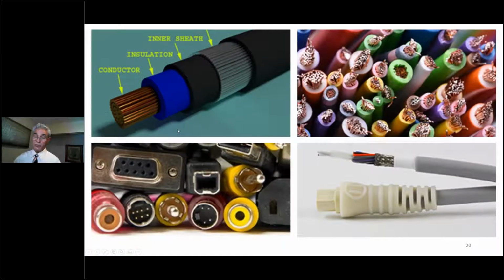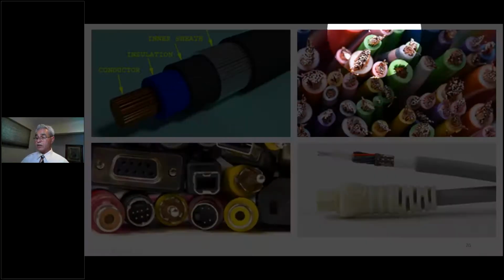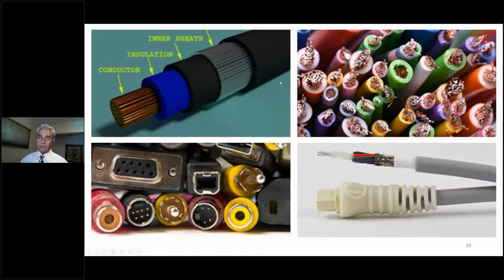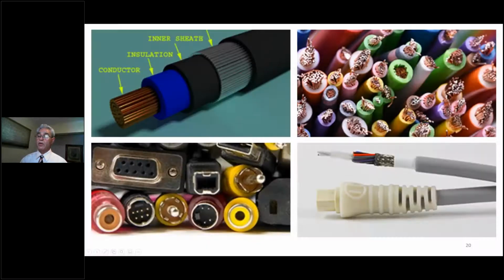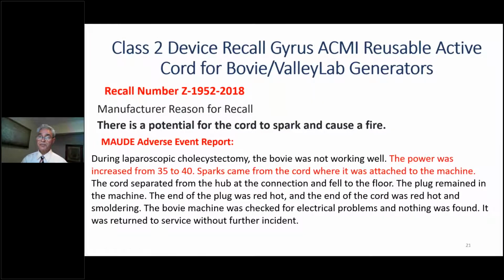We've been talking about the protective insulation. However, there are some reports of surgical fires or near misses where the actual conductors of those wires were getting damaged, breaking over time. Once you get to the end of the life, you have one or two of these strands left, then all of a sudden it breaks or carries too much electricity and you get a big puff and smoke coming at the end of that process.